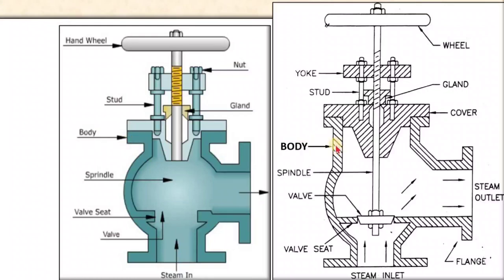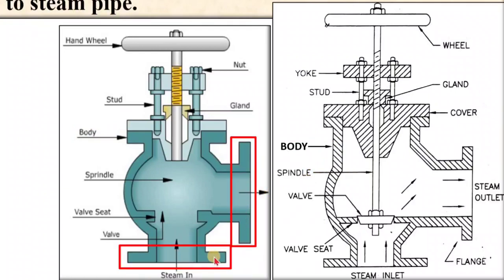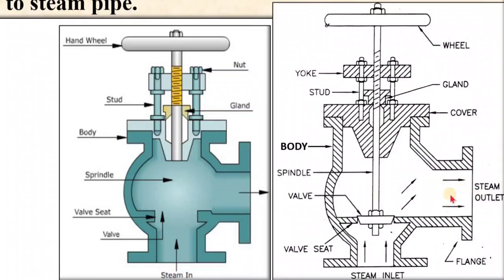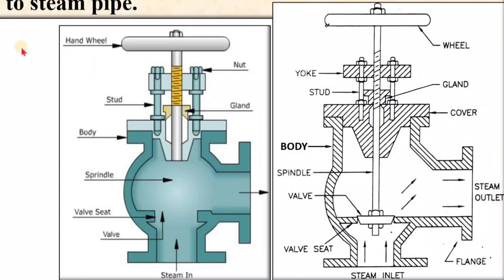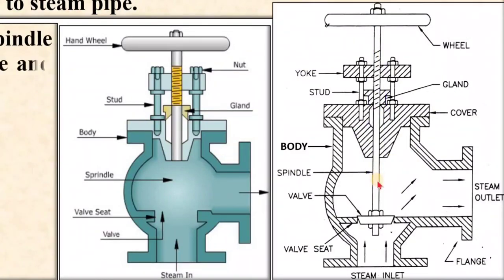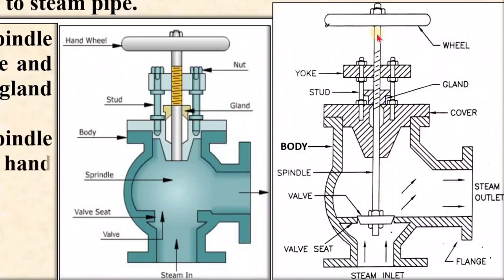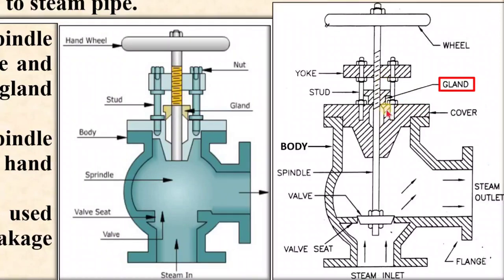It consists of a valve body — here you can see — made of cast iron, having two flanges at right angles to each other. One flange is bolted to the boiler at the top of the steam space and the other is connected to the steam pipe, from which steam can be sent to the engine or turbine. The lowest end of the spindle is connected to the valve and passes through the gland and yoke. The upper end of the spindle is connected with the hand wheel. The gland is generally used to prevent the leakage of steam.